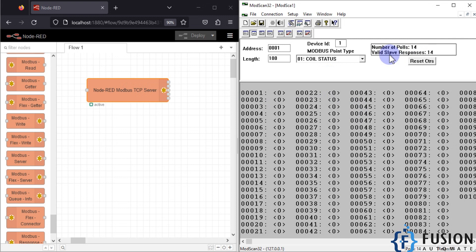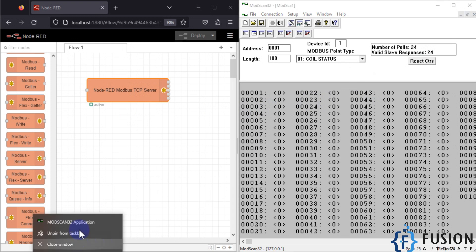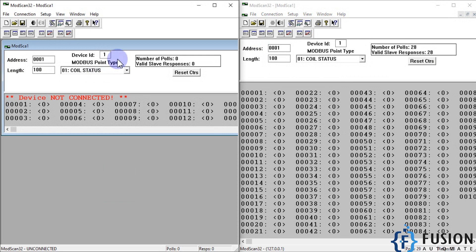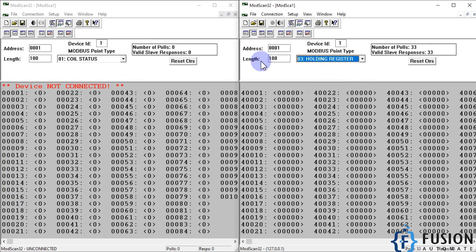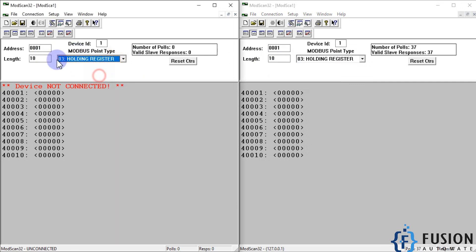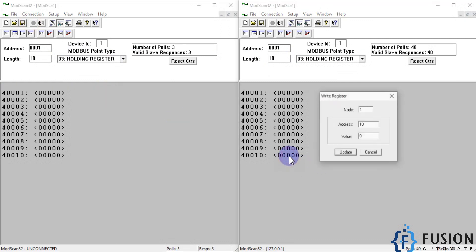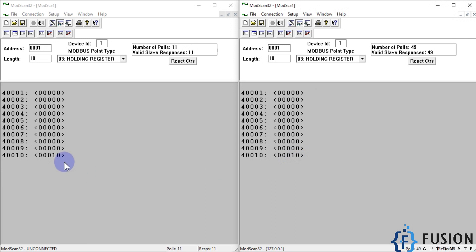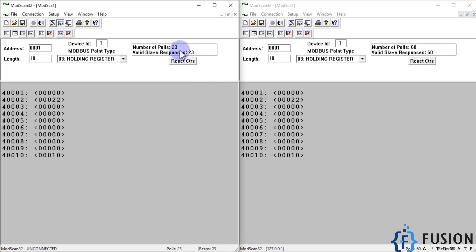You can see the number of polls equals the number of slave responses, meaning there is no packet loss. We are successfully connected to our Modbus TCP server. Opening a second instance of ModScan32, I navigate to the holding register and decrease the length to 10. Connecting again, if I update a value — say 10 — it reflects in the second session as well. Changing the value to 22 also reflects there, and the poll count equals slave responses confirming no packet loss.